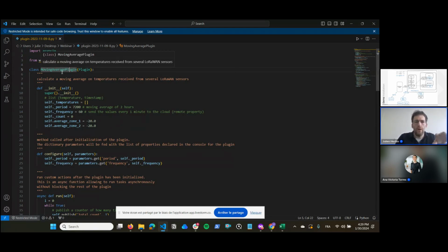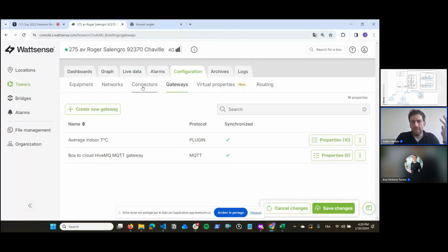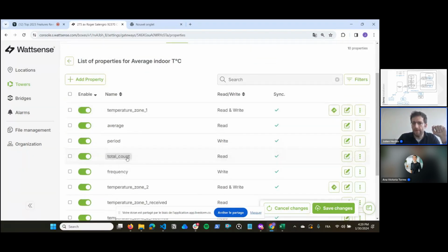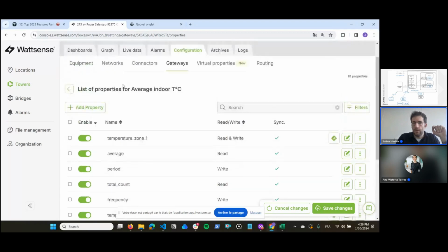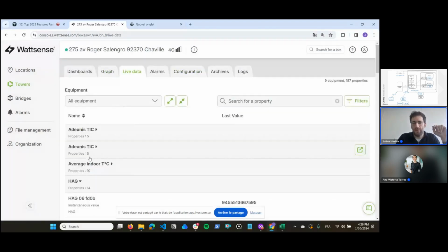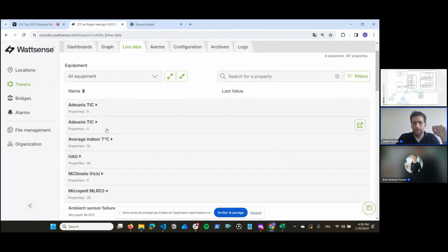For example, I'm calculating a moving average temperature if I want to redirect it to my boiler controller. I can compute the average indoor temperature of my building, north exposure, south exposure, and send it to the boiler controller to get an accurate indoor temperature. In your plugin you have different properties, and you can monitor them like any other properties in the console.